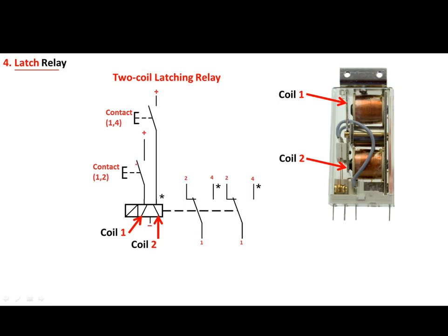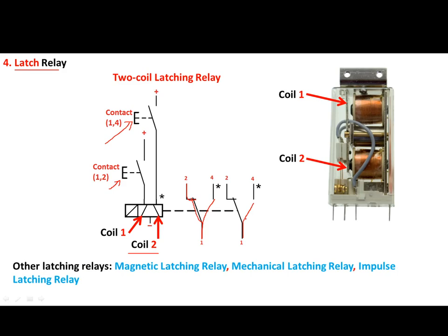For example, if the first button is pressed, energizing coil one, then terminal one will be connected to terminal two. However, if the second button is pressed, energizing coil two, then terminal one will be connected to terminal four. This is what we call a latch relay. Other technologies in this category include magnetic latching relay, mechanical latching relay, and impulse latching relay.